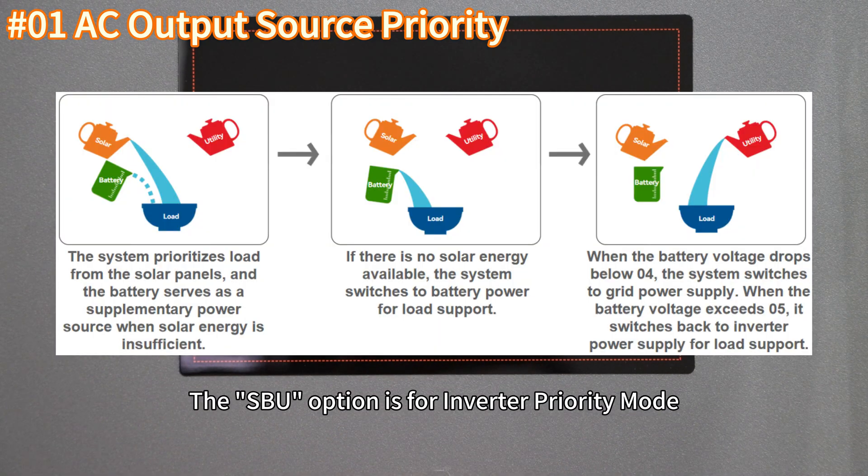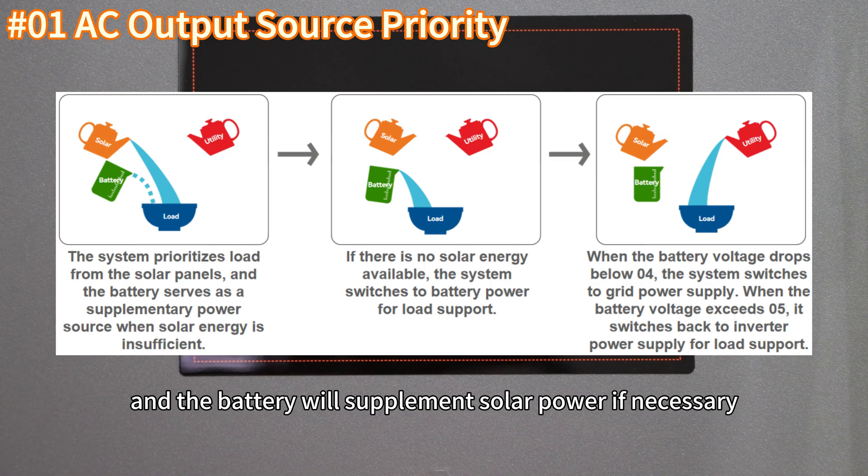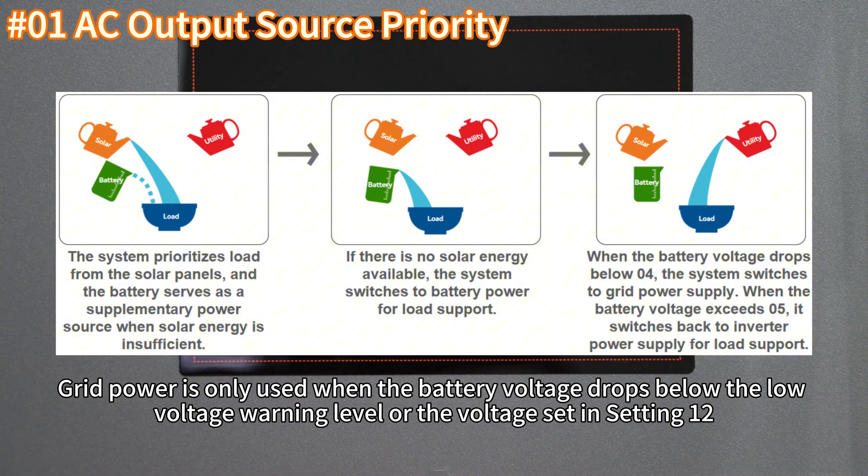The SBU option is also for inverter priority mode, where solar power is the primary source for load supply and the battery will supplement solar power if necessary. Grid power is only used when the battery voltage drops below the low voltage warning level or the voltage set in Setting 12.